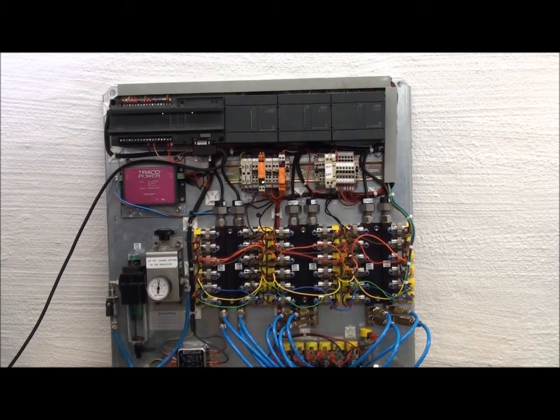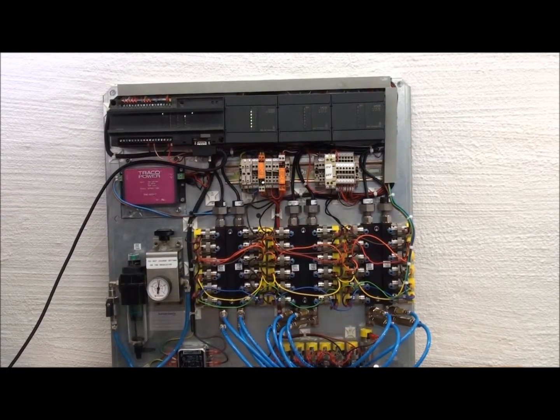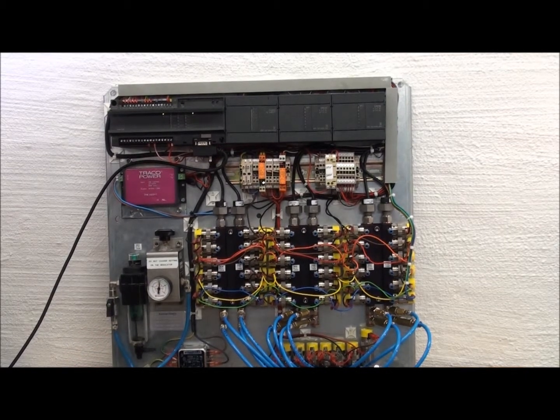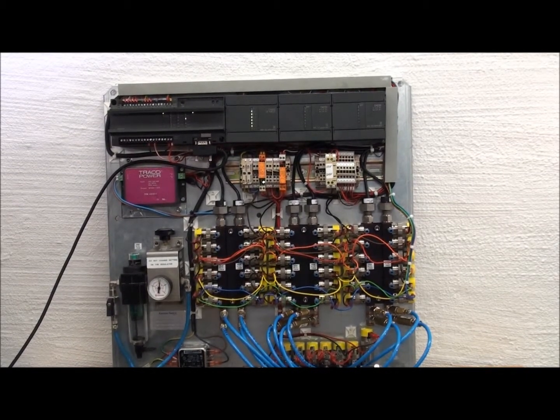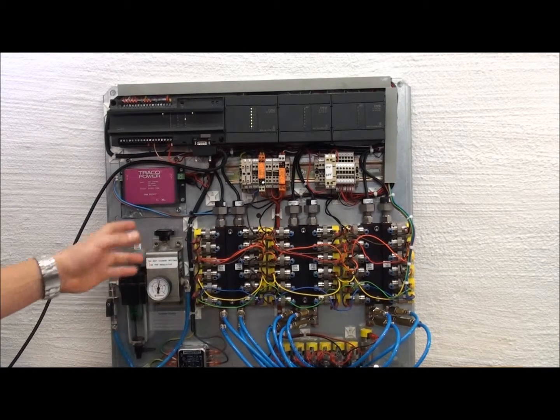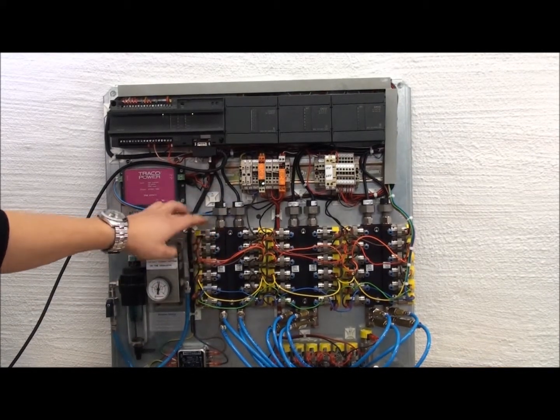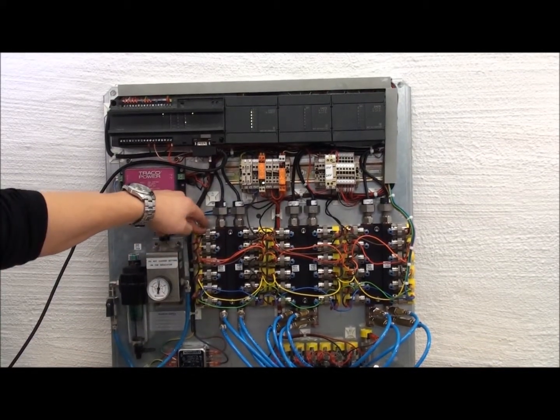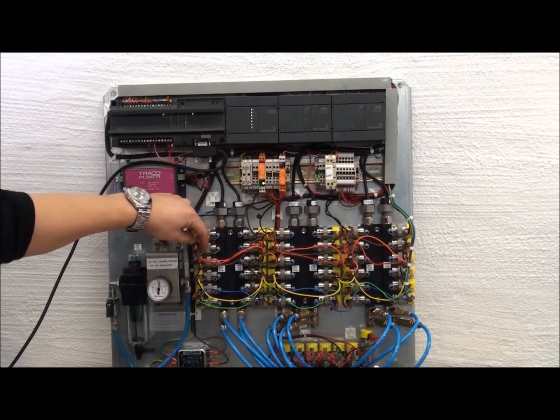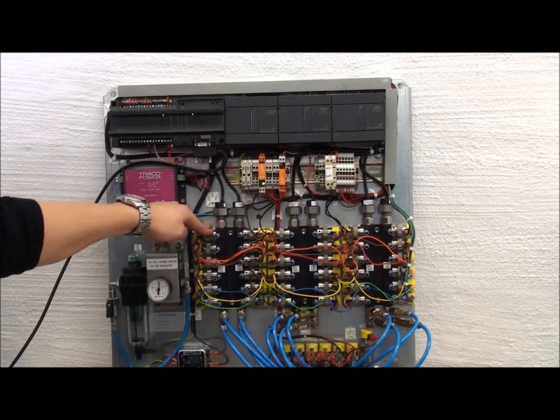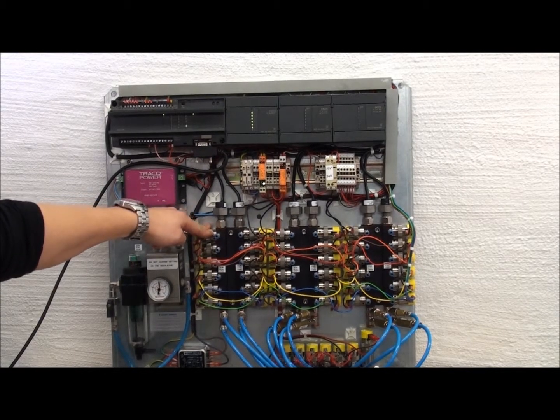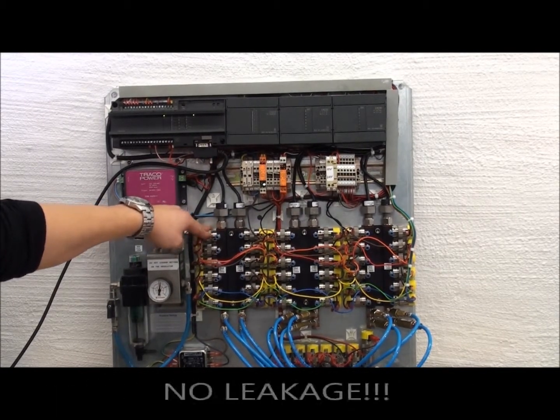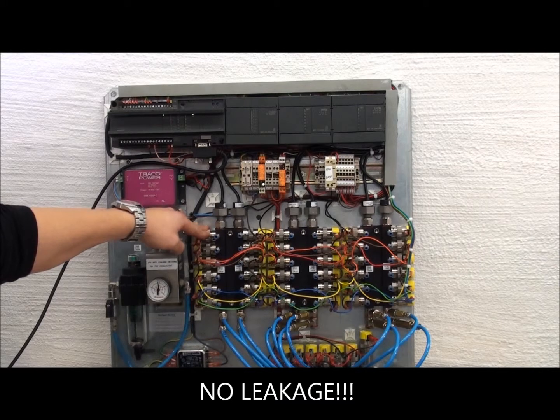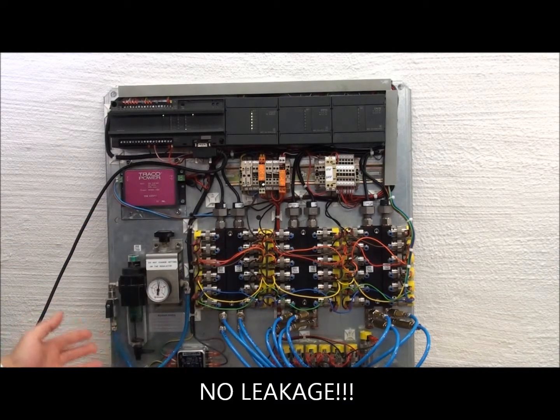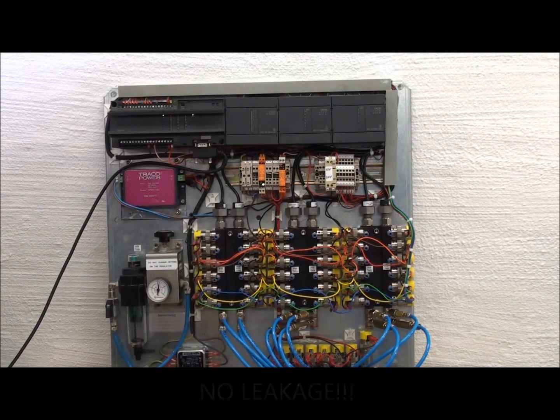In general, I think you should calibrate the system all the time when you do a service or a preventive service or whatever kind of service it is, because it's important for the accuracy of the system. You should never do a calibration if you're not completely sure that there is no leakage at all in the system. The minimal leakage in the system can cause that instead of calibrating the system, you just uncalibrate it. I mean, it will be just wrong and go backwards.